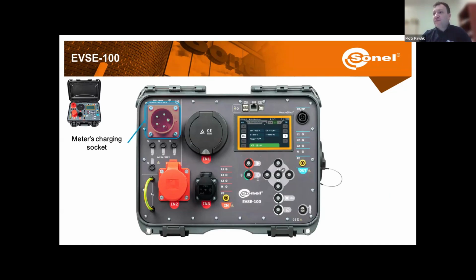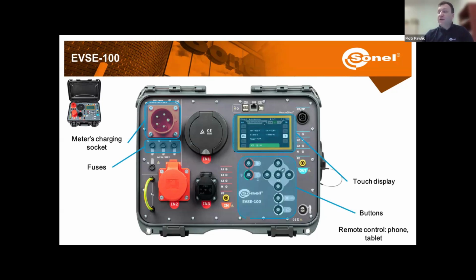Here, this is the charging of the meter. Here we have the fuses. Then we operate the meter using a touch display or buttons underneath, or we can operate it remotely using the app on the phone or the tablet. To connect it to the charging stations, we have different sockets: either a single-phase socket, a three-phase socket, or a socket with a type 2 outlet. We can also check the leakage current over here on this wire.